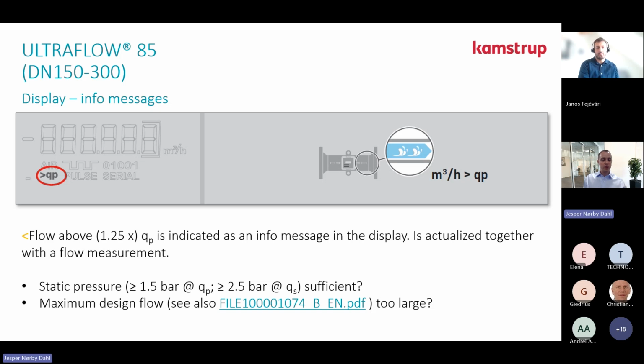Then there is this new small symbol telling you if the flow is 25% above QP; this small symbol will light up. It's very important for me to say it's not an error, it's an info. When you are running the flow sensor above QP, it is very important that you have a sufficient amount of static pressure, so you don't have any cavitation inside the meter. So it's an info for the installer or for the people running the units that if you're above QP, you have to make sure you have a sufficient amount of pressure.